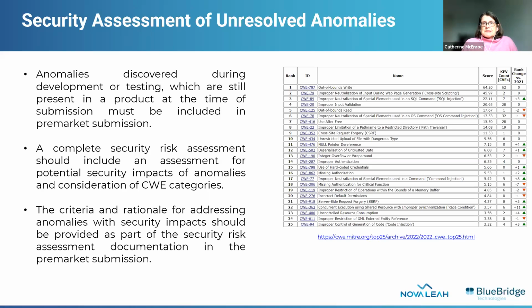So, for example, there could be a software anomaly that occurs sporadically. And from a software risk perspective, it's a low risk, but the potential impact of a threat coming along, deliberately seeking and exploiting that anomaly has to be considered and addressed in the context of the asset within your device and your patient safety. So you're still going to need to assess the potential impact on patient safety for all these unresolved anomalies and consider that information that is needed for submission. And again, the criteria and rationales for addressing the resulting anomalies with security impacts has to be provided as part of your documentation in the pre-market submission.